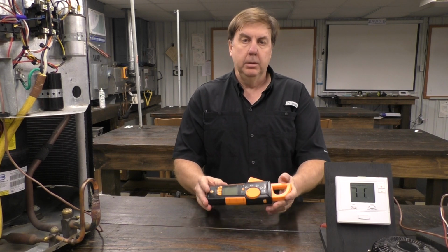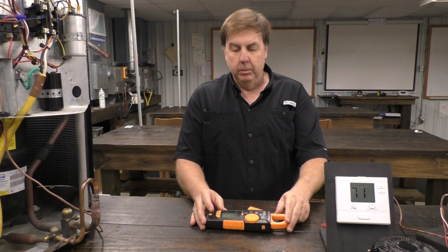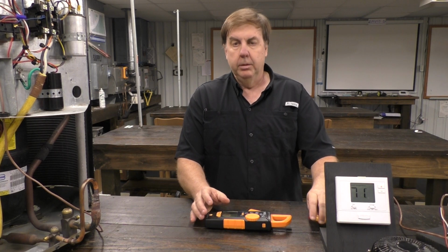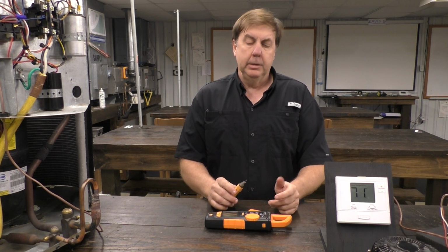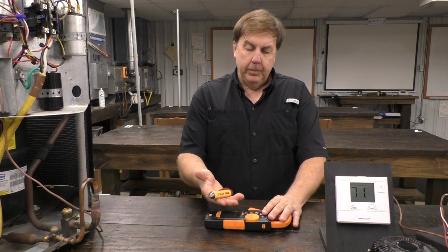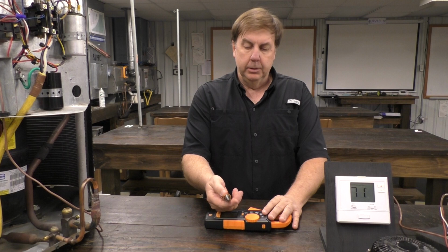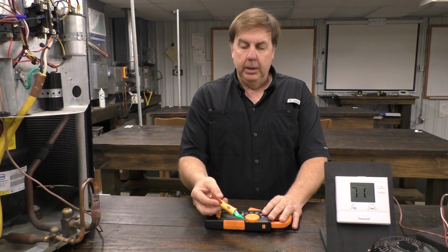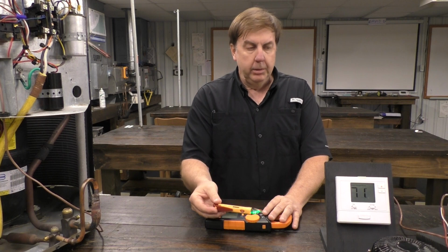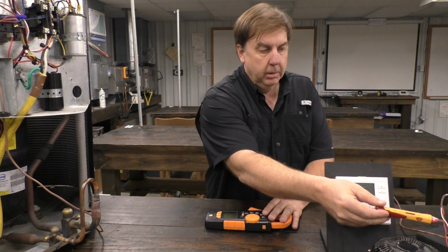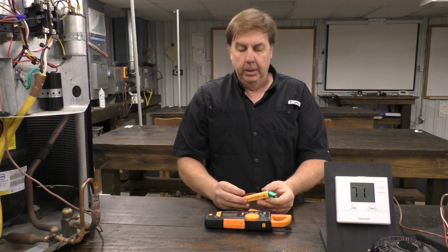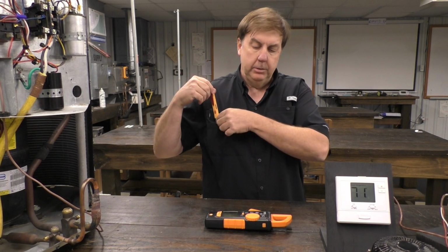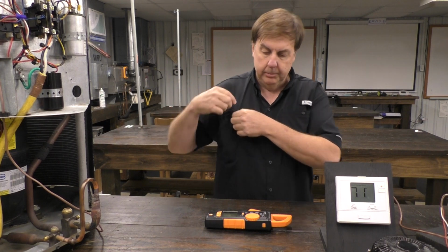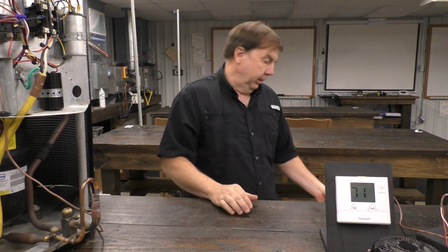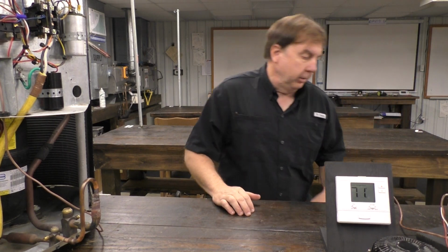I need to check my meter against a known source. Maybe I'll walk over to a wall outlet, or maybe I'll walk over to a unit that's running, or before I turn the power off, maybe I test this meter. I also can get inexpensively a proximity tester such as this one, which I can turn it on, keep it in my pocket when I need it, and hold it up to anything energized. If I hold it to any sort of power source that I'm wondering about and it goes off, it tells me that it's charged. That's a second device telling me that I might need to check it again. So the point being is we always verify, and we double verify so that we're safe.